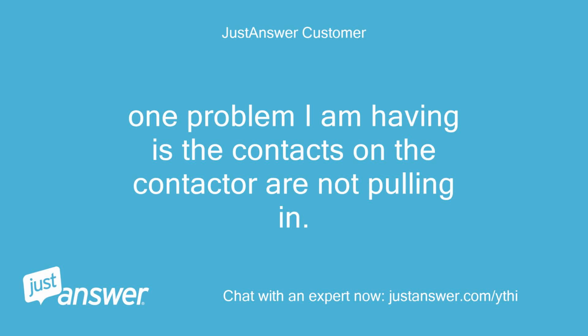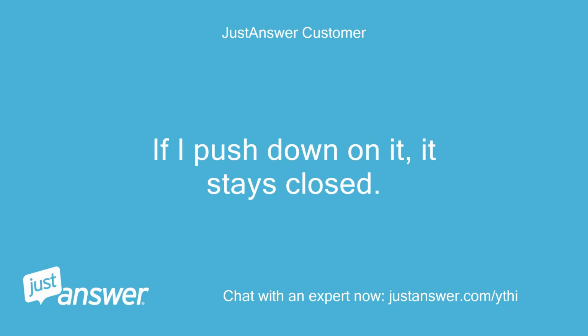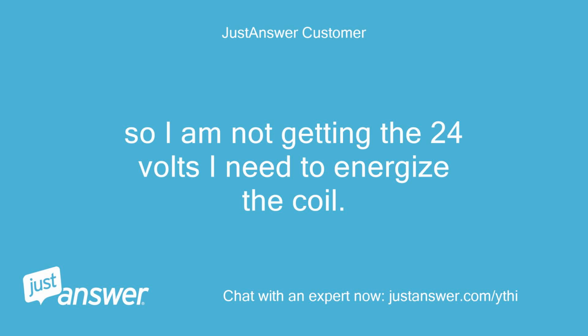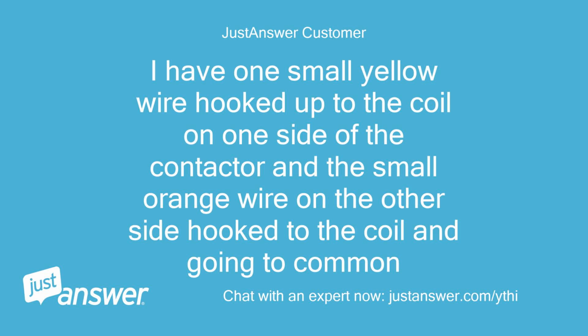One problem I am having is the contacts on the contactor are not pulling in. If I push down on it, it stays closed. So I am not getting the 24 volts I need to energize the coil. I have one small yellow wire hooked up to the coil on one side of the contactor and the small orange wire on the other side hooked to the coil and going to common.